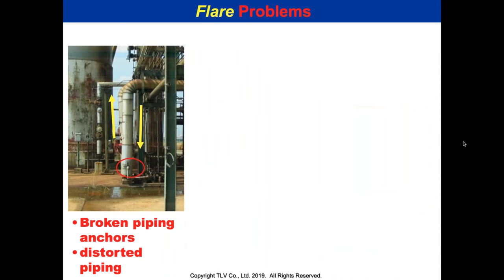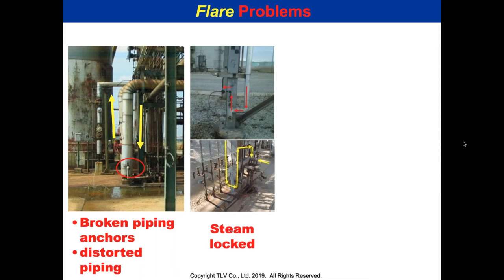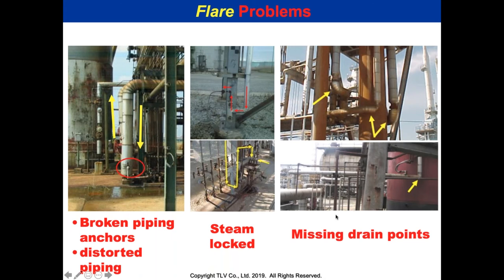When we see flare problems like broken piping anchors or distorted piping, that's caused by water hammer — it means the system isn't draining. It might be that the trap was installed wrong or improperly selected. When you have a vertical rise going up to the trap, you get a steam lock — you want the trap down low, not up high. Sometimes there are missing drain points. It's inexpensive to add a trap relative to replacing a flare tip at one and a half million dollars.